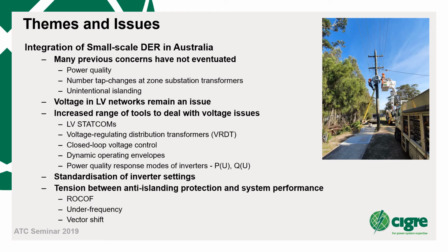However, there are an increasing number of tools available to network owners to mitigate such problems. Whereas in the past, the solution to a voltage problem may have been to upgrade the network, other options available now or that are being trialled include low voltage StatComs, voltage regulating distribution transformers, and closed loop voltage control. PV inverters also include features to help with voltage management, such as the so-called power quality response modes.